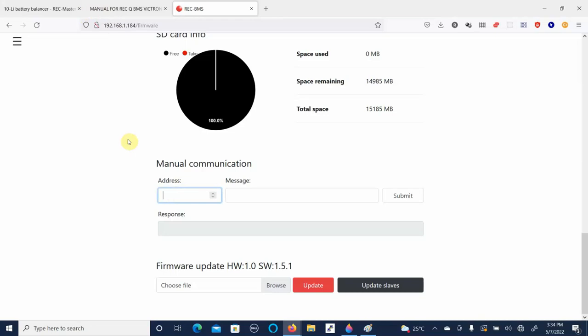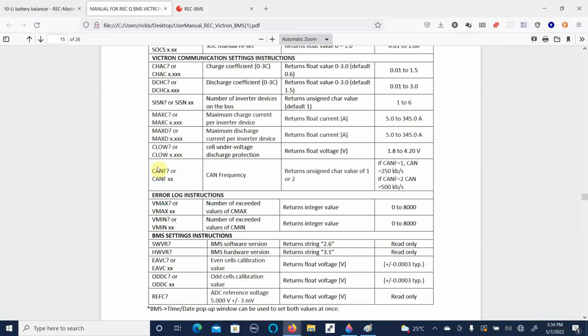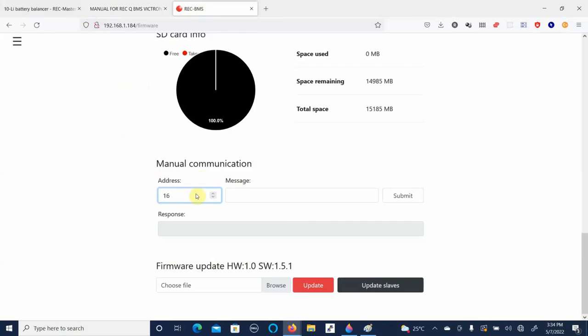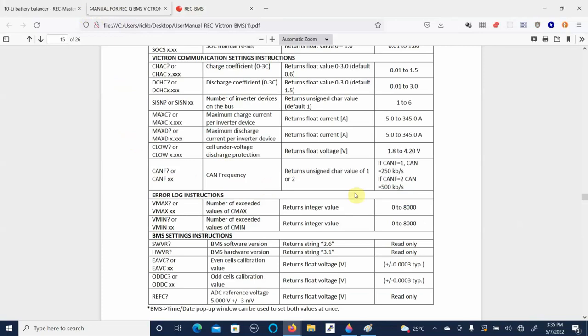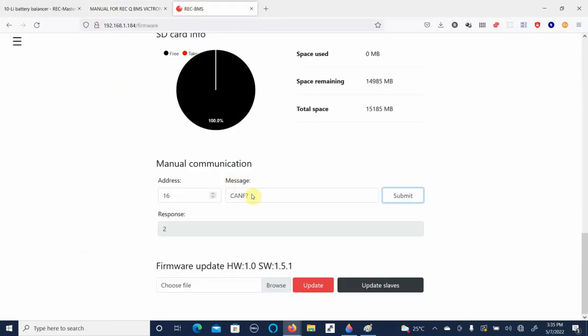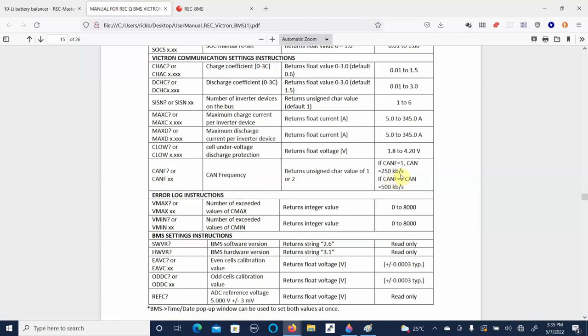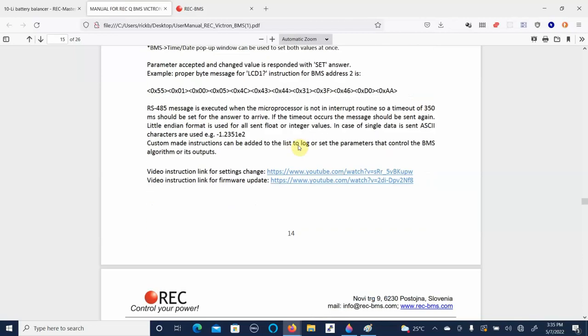So in this case, let's say we needed to change or even look at the CAN frequency. That would be CAN F question mark. So we type in address number 16, and in capitals CAN F question mark. Submit. And we got a 2 back. So we look at the manual and we see that 2 tells us that our CAN frequency is set to 500 kilobaud. Let's say we wanted to change that to 1. We go CAN F space 1, submit. We got a response of OK. Now we can go back in and hit the question mark just to verify it. And we can see now that our CAN frequency has been set to 250K as per the user manual on page number 14.